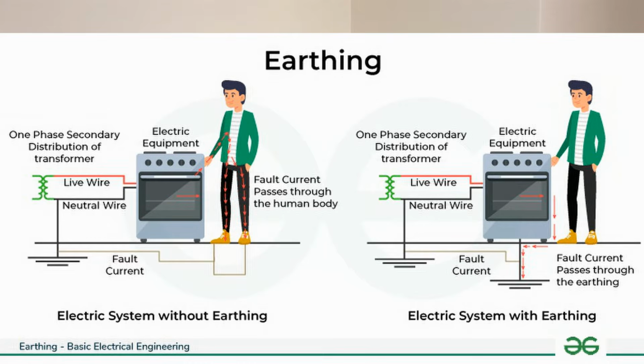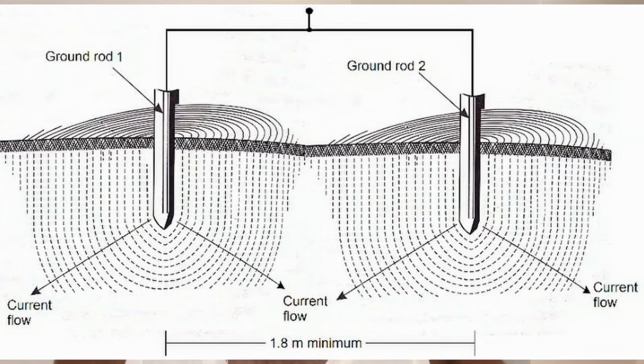Most homes try to fix earthing after the house is built - well, some homes, not most. That usually means one shallow earth rod, and the earth resistance didn't comply - it wasn't less than 10 ohms. The earth rods are too close together. It doesn't work: dry soil, poor resistance, no redundancy. The right chemicals were not put into the ground to help the earthing resistance. This works on paper, but not during a lightning strike or major faults.